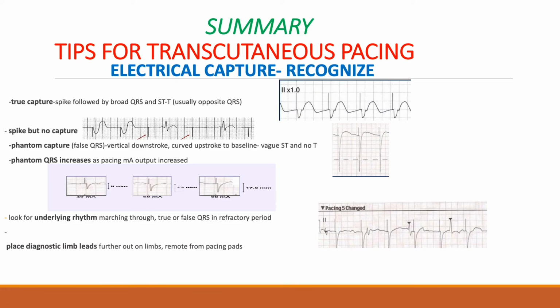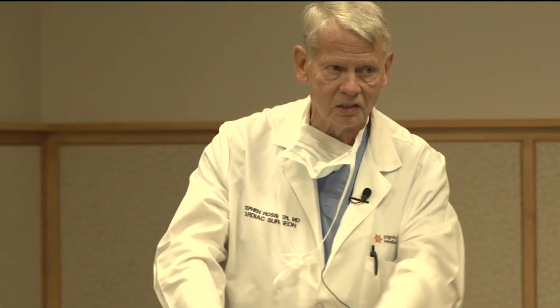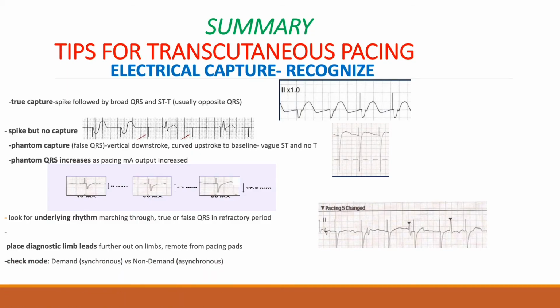One thing you can do, if you're having a problem with it, is try putting your diagnostic limb leads a little further away to get away from some of the artifact. It helps sometimes. And as we talked about, this does have a demand mode. So if you aren't getting routine capture, it may be because it's being suppressed, being inhibited because it's in demand mode, where it's saying, oh, I see something electrical going on, I'm not going to pace. So check that.